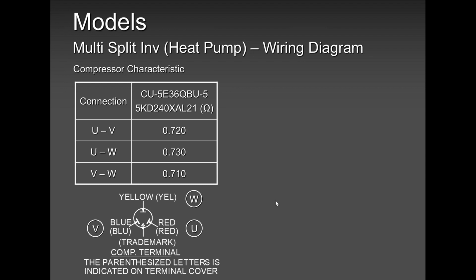Then comes the compressor. If you are suspecting the compressor is defective, check the coil. But I'll tell you, in most of these inverter-driven compressors, they very rarely go short to ground. I have not seen one yet. I have seen the older compressors, not the inverter compressors, the normal central compressors. They go short to ground. But the inverter I've yet to see. Mostly they seize, mechanically seized. But the winding reads good. And mechanically seized, I can tell you one thing. It's oil return. There was poor or no oil return that killed that compressor.